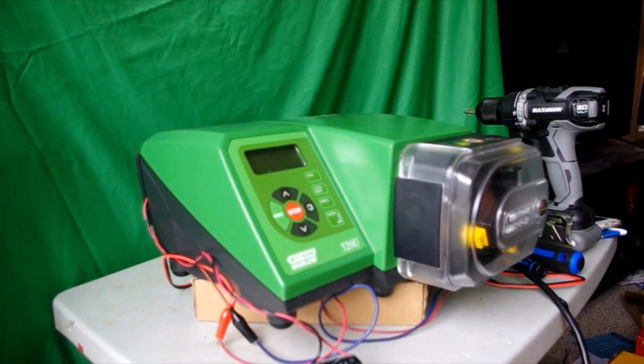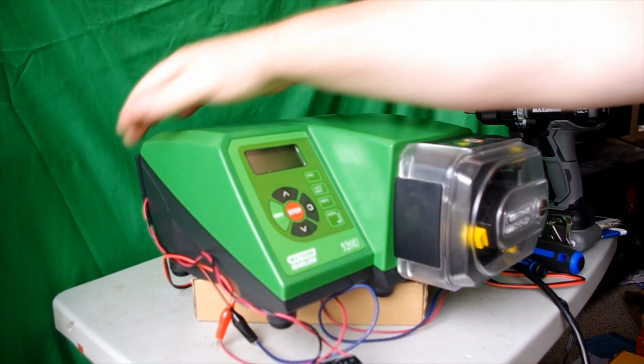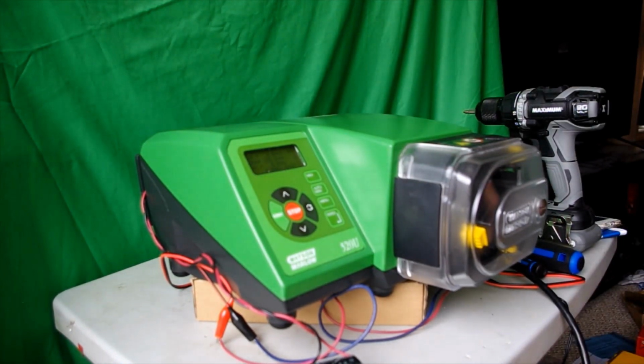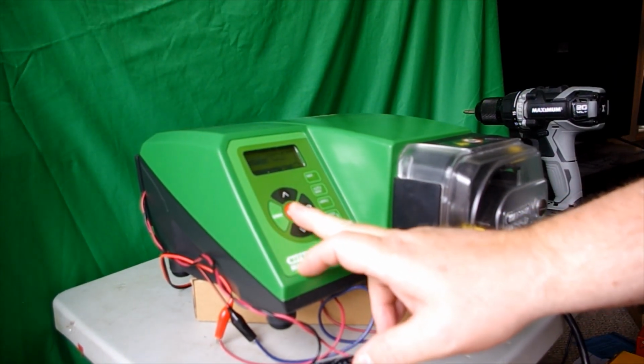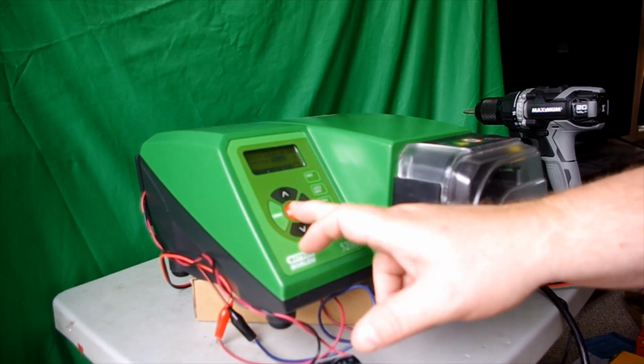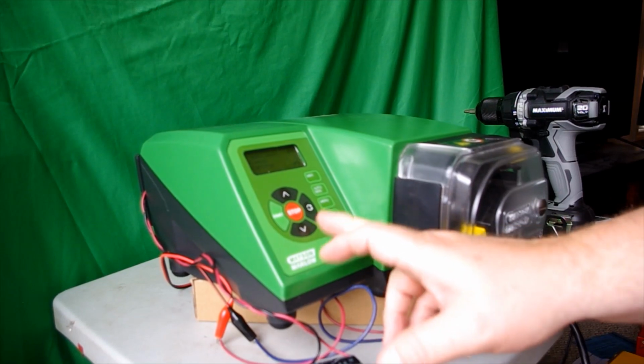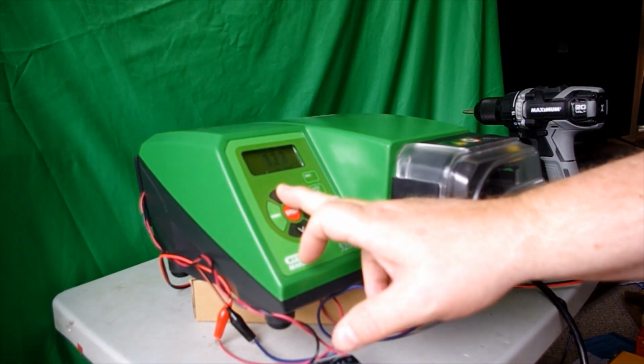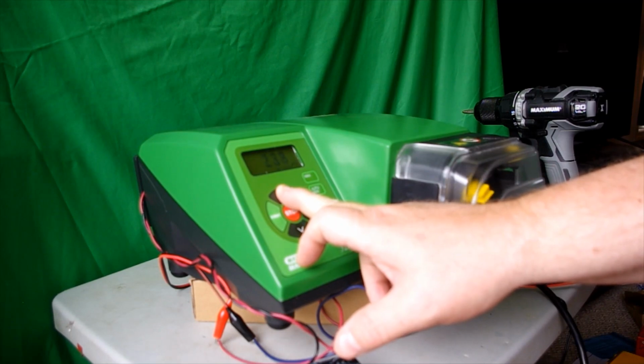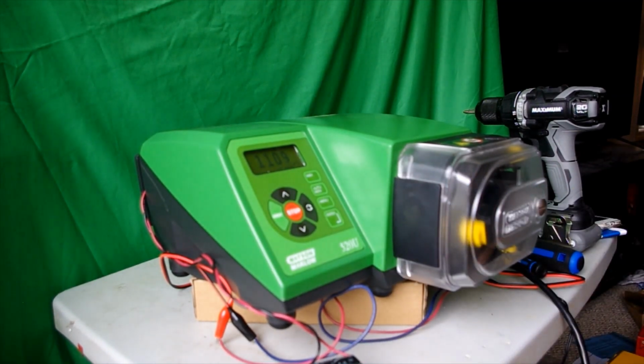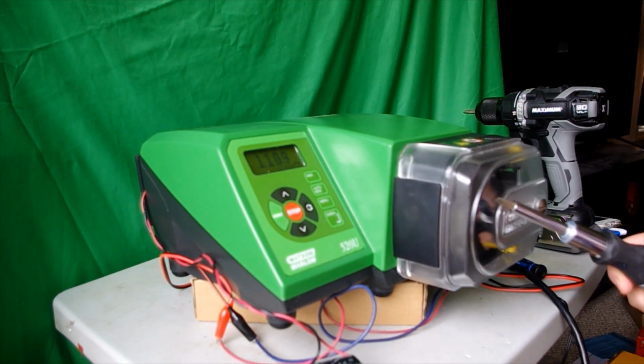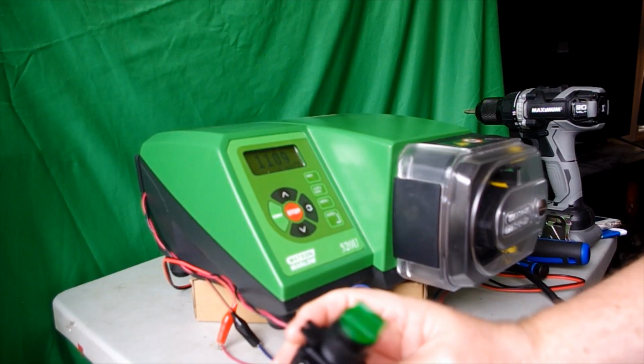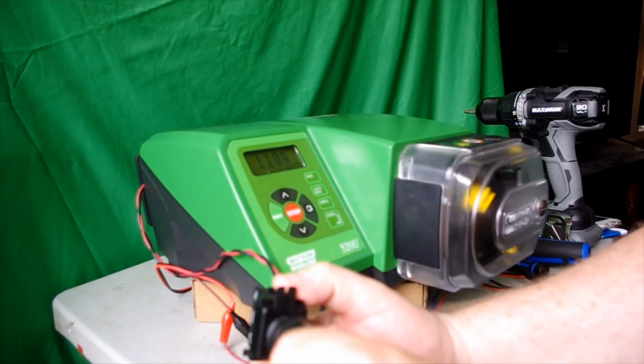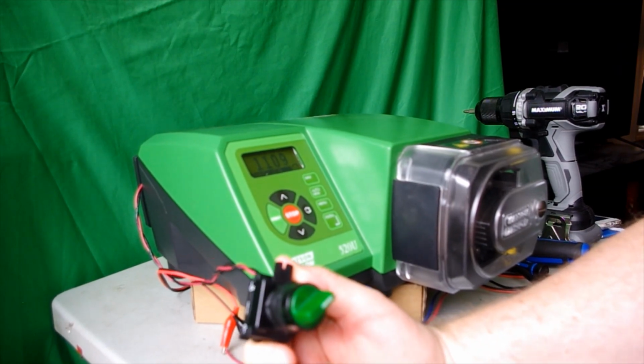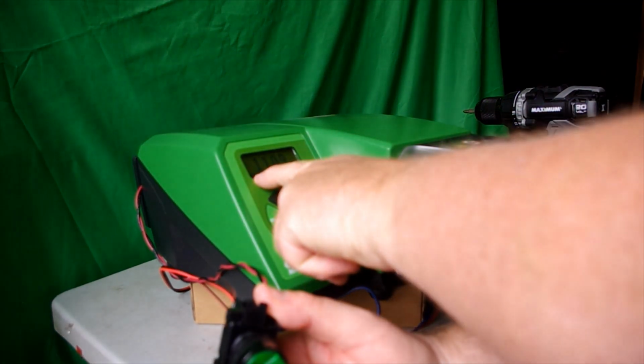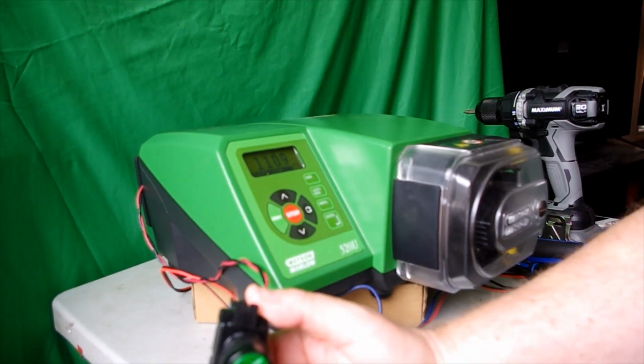So now that we have the remote start-stop switch wired, we would turn our pump back on, and I could press start or stop, in this case run the pump in manual mode. I'm going to do some work, and then I press enter. And now if I start my pump, turn up the speed, in this case in milliliters per minute, I'm in volume, and let's set her at 1,000 milliliters roughly. So if you notice here, the rotor is turning. I have a switch engaged. It could be through your SCADA system, but for demonstration purposes, I'm using this switch. And if I switch the switch off, you'll see on the display it says remote stop. And as you can tell by the rotor, it is not running.